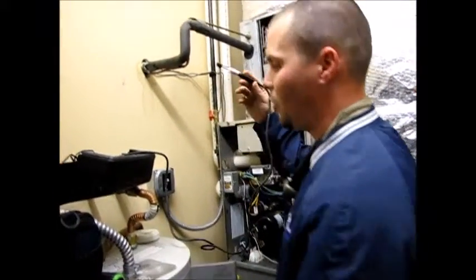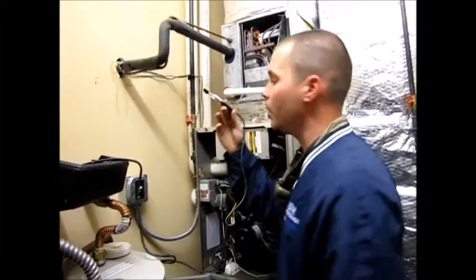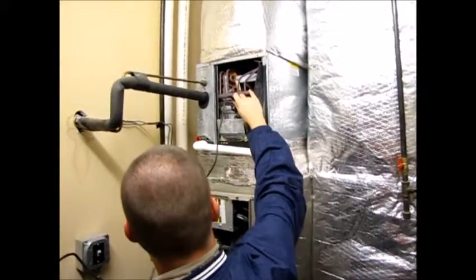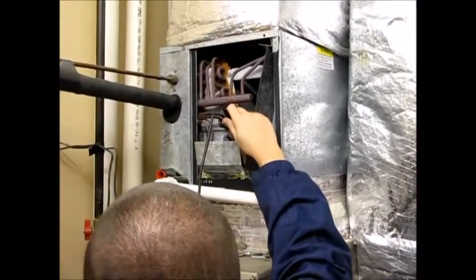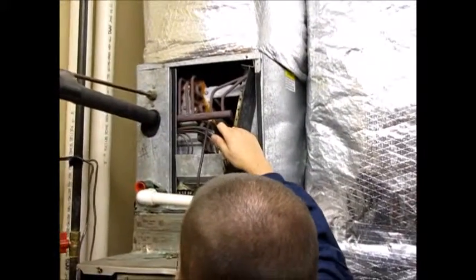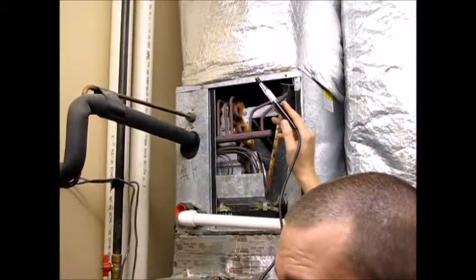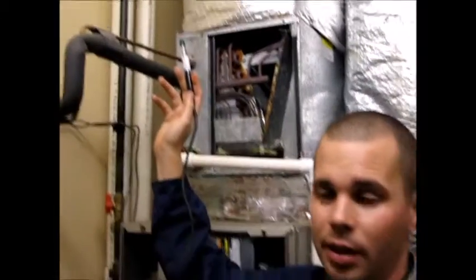Just to give you an idea, as you can hear it chirping, it's got a steady chirp. What these will usually do when they indicate that there is a leak in the system is you can notice a drastic change in the pitch and the frequency of the device, showing that we do have a confirmation of a leak in the system.